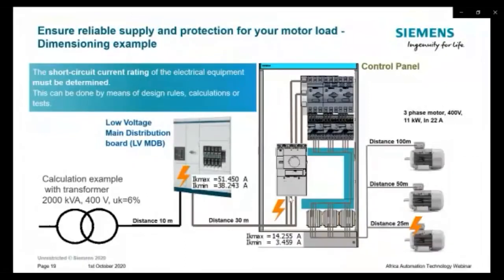So once you have a specific power supply, here in this example shown with a 2000 kVA power transformer, you can go for the calculation of the maximum and minimum short circuit currents. For this example, it appears here at the main distribution board with a distance of 10 meters to the power transformer to a maximum of 51.45 kiloamps. And it reduces towards the connection point at the motor control here to 14.25 kiloamps here at the control panel. It further reduces here towards the motor load.